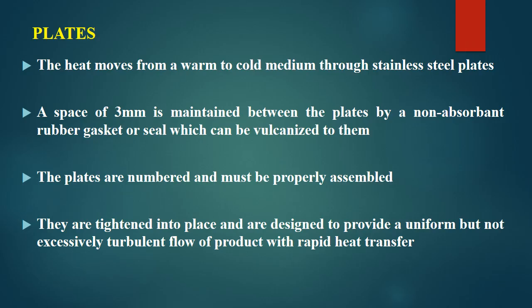Here are some of the details about the plates which I have already explained. The heat moves from a warm to a cold medium through stainless steel plates. A space of 3 mm is maintained between the plates by a non-absorbent rubber gasket or seal which can be vulcanized to them. The plates are numbered and must be properly assembled as per that order. They are tightened into place and are designed to provide a uniform but not excessively turbulent flow of product with rapid heat transfer. So these are some of the specifications about the plates.